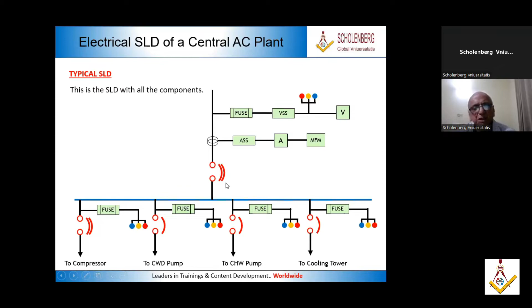Now, take a look at this SLD. This is the main cable coming in. Single line diagram means it is showing you only one phase. Every phase will have a fuse. Now we have the voltage selector switch and a voltmeter. This phase will have a voltmeter, this phase will have an indicating light, and this phase will have a voltage selector switch and a fuse. Same with the ampere meter. For an ampere meter, we'll have this current transformer, ampere selector switch, multifunction meter. Then we come to this. This is the MCCB. Then this is the bus bar.